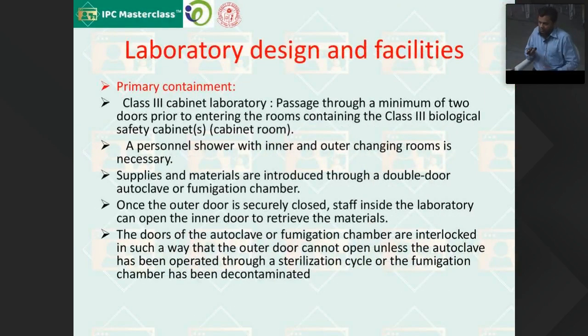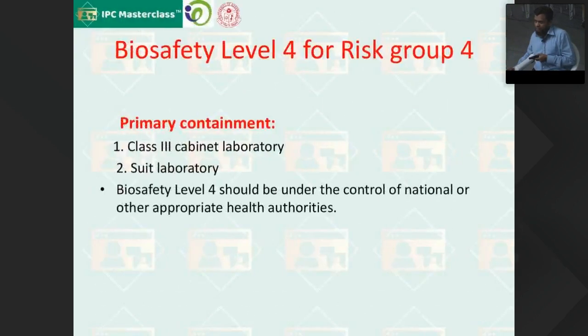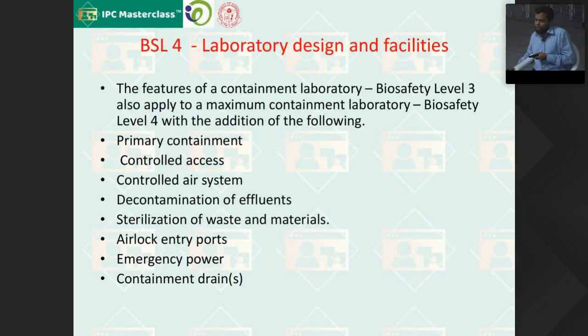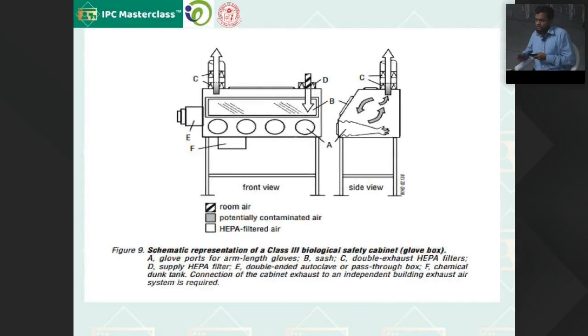If you see the primary containment in the class 3 cabinet laboratory, passage is through a minimum of 2 doors, entering into the containment containing a class 3 biosafety cabinet. So in the class 3 cabinet laboratory, we have a class 3 biosafety cabinet. I've shown you just now the class 3 biosafety cabinet. If you see here, this one, the class 3 biosafety cabinet, you have a glove port where you extend your arm with the gloves and you process. It is totally closed. There is no recirculation, 100% exhaust, and hands can be entered only through the port. This is what we use in BSL-4.